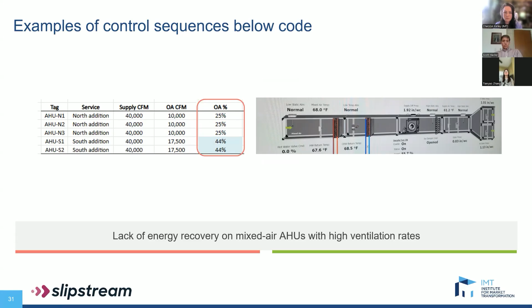And for the next measure bucket, nighttime shutdown and setbacks. These are all low-hanging fruit that would be pretty easy to implement and save a ton of energy. We found that a handful of buildings were operating 24/7, even though they were unoccupied overnight. The common theme for these buildings was that they were all originally designed to meet code, but the design sequence didn't actually make it into the BAS programming.